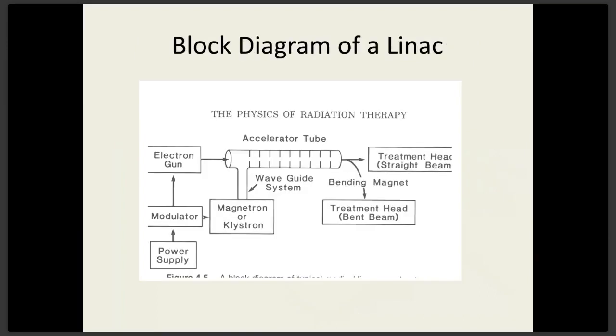A LINAC breaks down into certain key components. The electron gun is the source of electrons. The accelerator is the 4-foot long tube that actually does the acceleration with a series of cavities. Of course, you have to have a magnetron or a klystron to pump the microwave into the accelerator. So that's the job of the magnetron or the klystron. And the modulator is what causes the magnetron and the klystron to work effectively. And the modulator also pulses the electron gun so that the bunch of electrons hits those cavities at just the right point in time where they undergo push, pull, push, pull, push, pull.